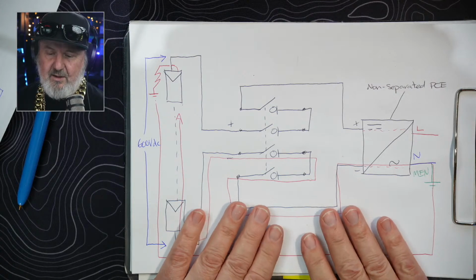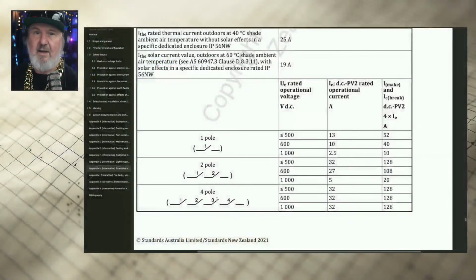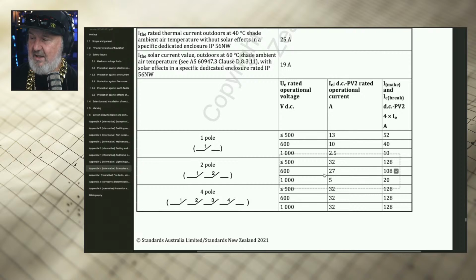Yes. So coming back to 5033. In this example, we're going to look at 2 poles in series, so a 4-pole DC switch with only 2 poles switching when there's a fault condition. And there's our voltage and current ratings for open circuit voltage, our operating current, and our I make, I break current. Look how big the difference is between operating current and I make, I break. It's huge.